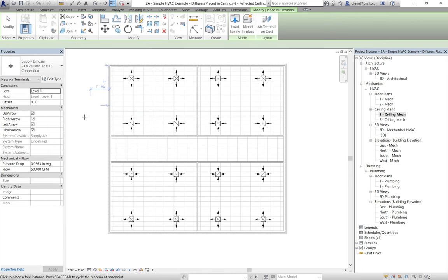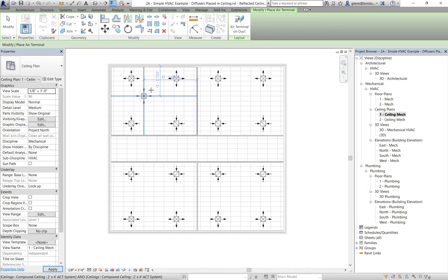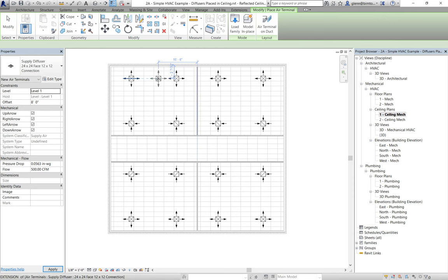There's an interesting debate about whether to set diffuser elevation relative to level two from below or level one from above. If you know they always want to be eight feet above and you're not sure about the floor-to-floor height, it's better to reference them off the level below. If you know the sandwich thickness is always a set number of feet below the level above, you can do it that way. It's just whichever direction things are more likely to flex — either the bottom or the top.